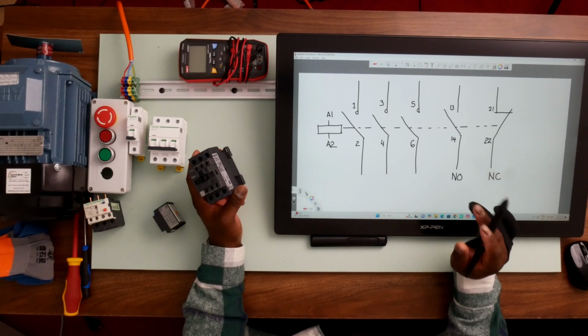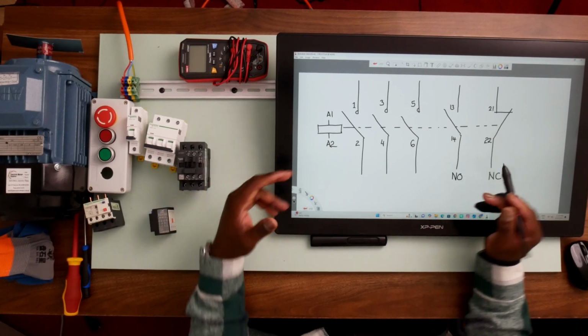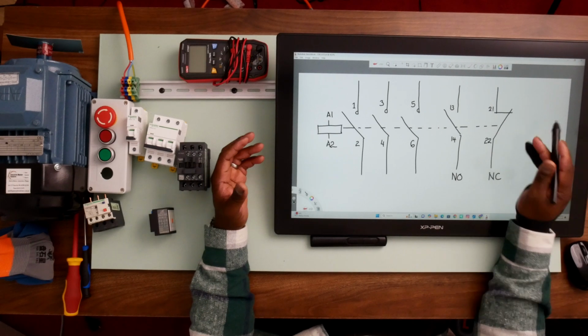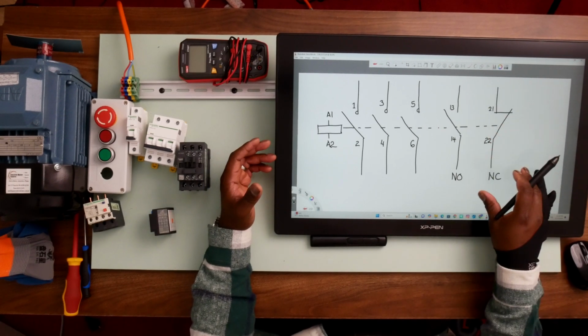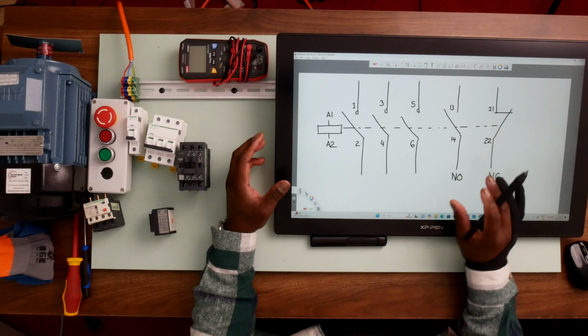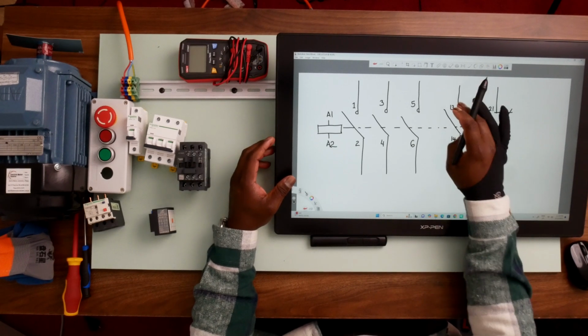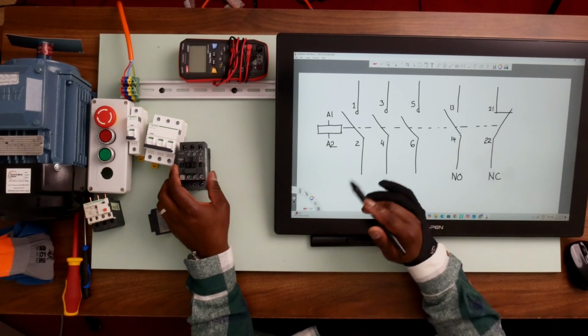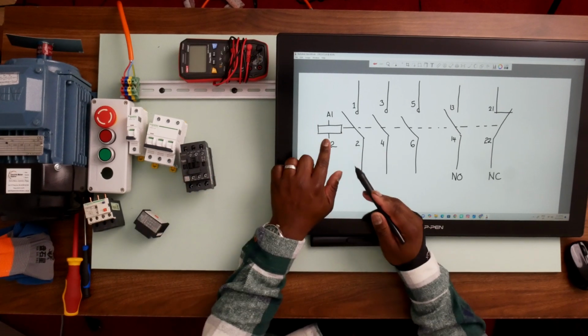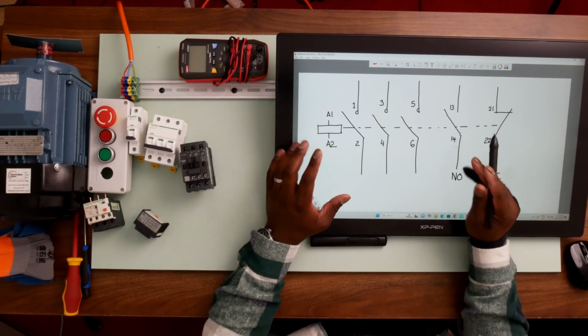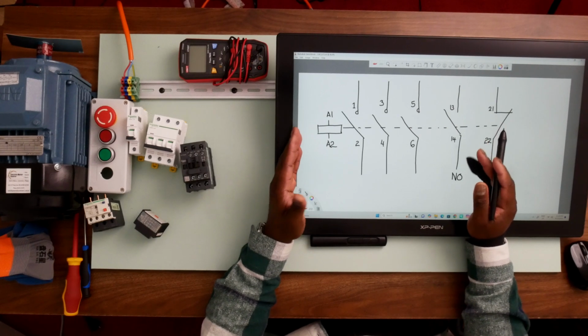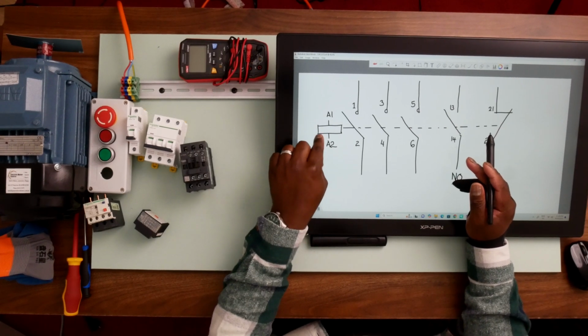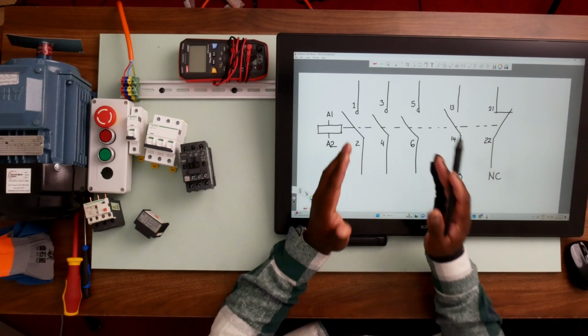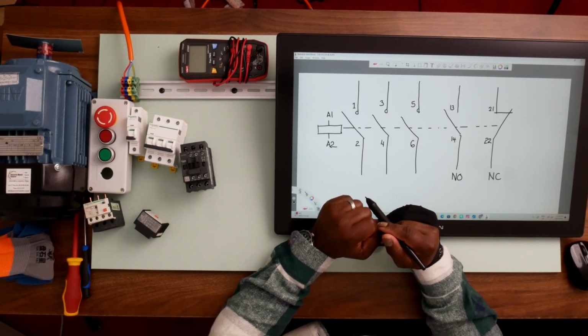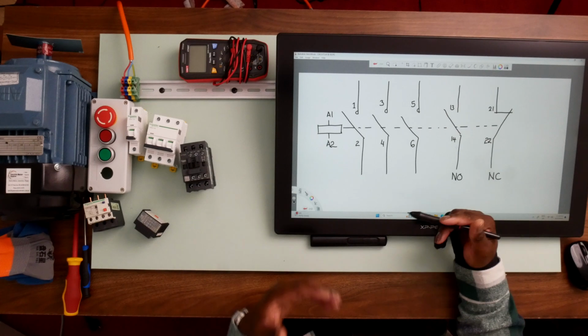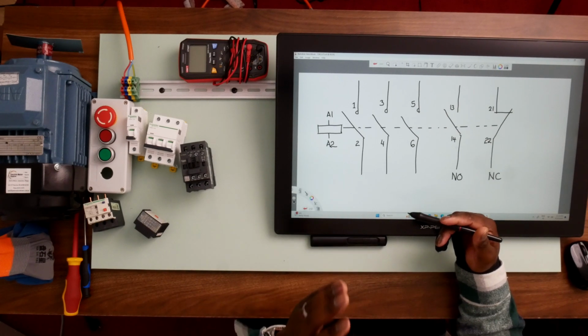But for a simple direct online starter that we're going to do today for this activity, we don't necessarily require the normally closed contact. On the control side, we only require the normally open contact, which is 13 and 14, and the contactor coil. So the contactor coil and 13 and 14 here are part of the control circuit. This control circuit operates the contactor coil, which in turn operates the power contacts on the contactor itself. I know we are going to gain more clarity as we start to utilize these symbols when we are drawing the actual circuit.